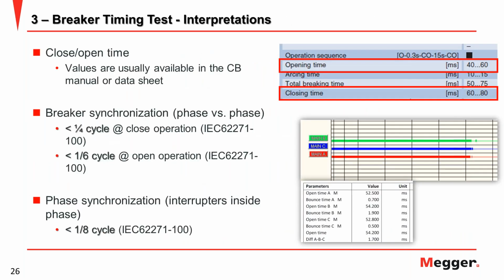Yeah, they can follow this standard. If you have a 50 hertz system, it means there is 20 milliseconds per cycle. So for the close operation, the maximum difference between pole A, B, and C is 5 milliseconds. But for the open operation, it should be less, around 20 divided by 6, I think. 3.3 milliseconds is the maximum limit for the open operation difference between poles.